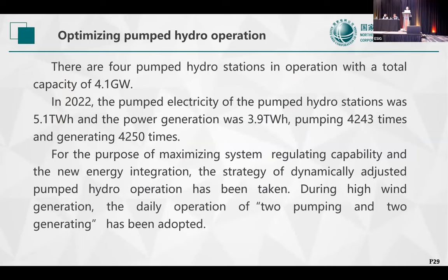Now come to the pumped hydro operation. There are four pumped hydro stations in operation with a total capacity of 4.1 gigawatt. In 2022, the pumped electricity of the pumped hydro stations was 5.1 terawatt hours and the power generation was 3.9 terawatt hours. Pumping times is 4,243 and generating times is 4,250. And during high wind generation, the daily operation of two pumping and two generating has been adopted.